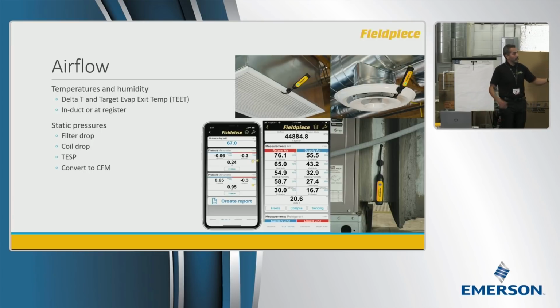So we can look at the air going across the evap coil in two different ways. We can look at a straight delta T, just looking for a differential, and we can look at what a target is supposed to be and then compare it to the actual value. Simple. Now, if you had a situation where you weren't going in duct or there just wasn't metal, so the magnet wouldn't be effective, you can slide the magnet up and there's a hook on the back that you can clip onto a fin of a register as you put it inside, and it just stays there. Okay? Now, it's probably what we're going to do for something like this. Usually it's something that's on a roof.